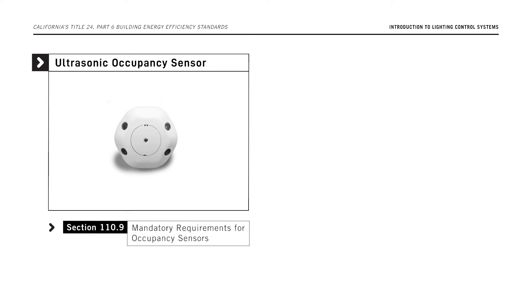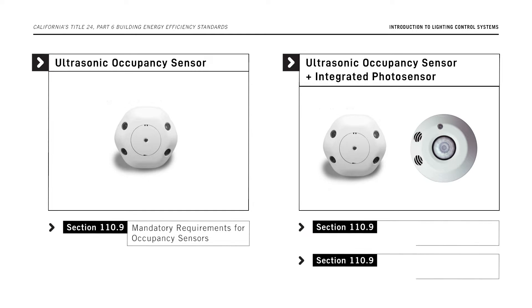For example, if an ultrasonic occupancy sensor is installed to comply with the shut-off control requirements in the Energy Code, then it also must comply with the specific device requirements in Section 110.9. If that same device contains an integrated photo sensor to serve as part of a daylighting control system, then it also needs to comply with requirements for a daylighting control contained in Section 110.9.